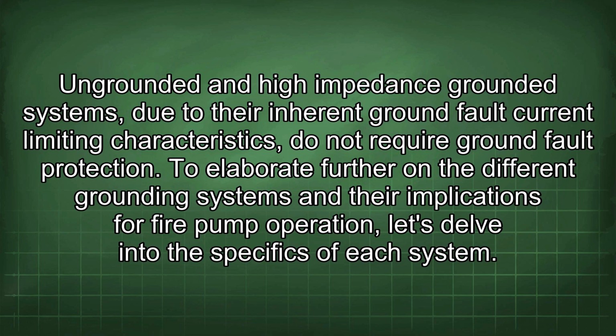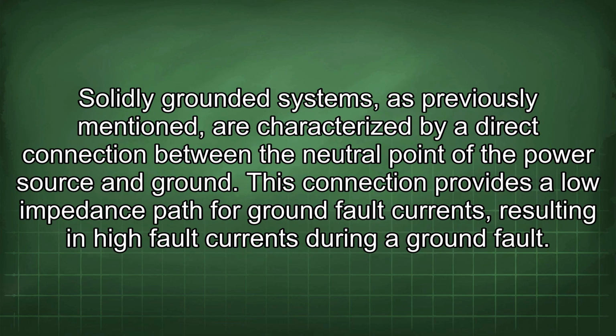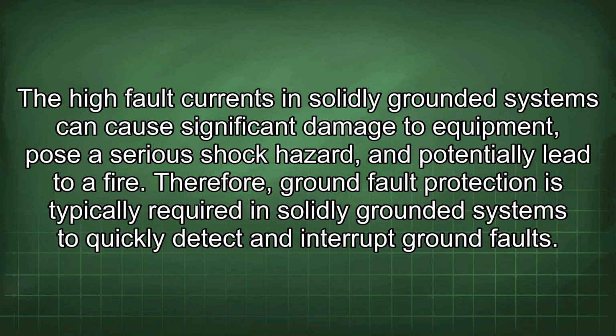specifics of each system. Solidly grounded systems, as previously mentioned, are characterized by a direct connection between the neutral point of the power source and ground. This connection provides a low impedance path for ground fault currents, resulting in high fault currents during a ground fault. The high fault currents in solidly grounded systems can cause significant damage to equipment, pose a serious shock hazard, and potentially lead to a fire. Therefore, ground fault protection is typically required in solidly grounded systems to quickly detect and interrupt ground faults.